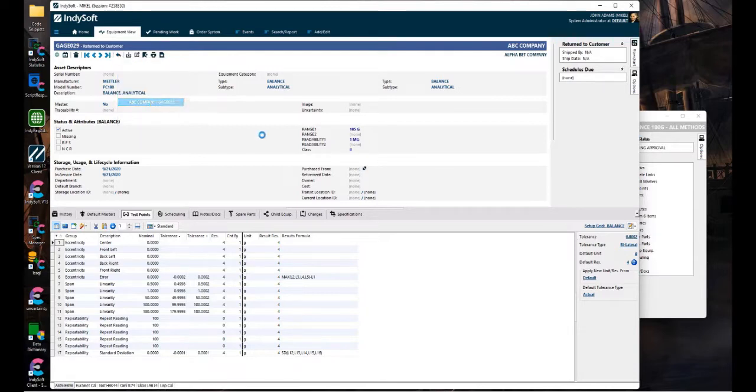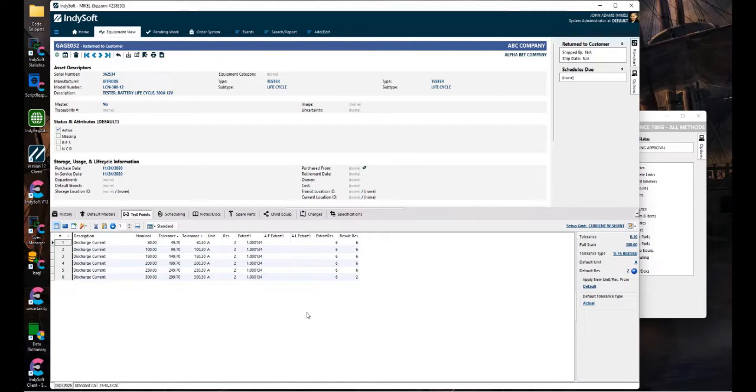Another situation will be different quality system requirements. I've got some customers that may require 17025. I've got some that use a standard calibration, and maybe I've got a few customers that need the Z540.3 where I'm calculating PFA and things of that nature. So again, the whole idea is to try to reduce the number of templates that you have to deal with.